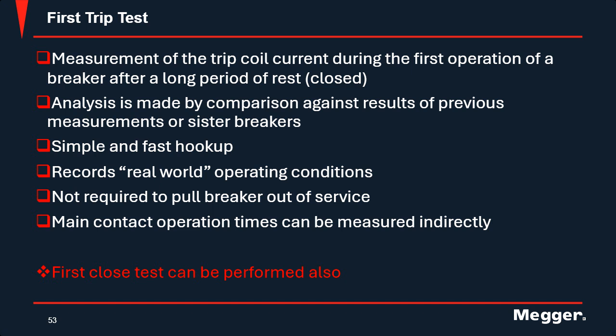So the biggest benefit of using the first trip is it gives you real world operation conditions. So what's it going to look like if there is a fault and that breaker has to open? Like I said, if it hasn't been operated in years, the first test will reveal if the circuit breaker is slow due to problems in the mechanism or the coil amperage, or if there's any corrosion or dry grease within your linkage. With the traditional method, you usually already have the breaker open, and they might have operated it a couple times. So all those sore spots, that dry grease, is already knocked off, and the breaker is back to operating within specs.